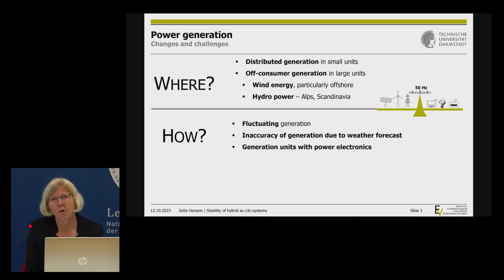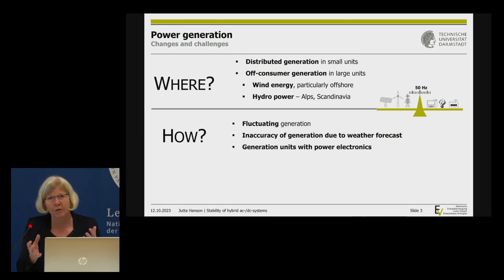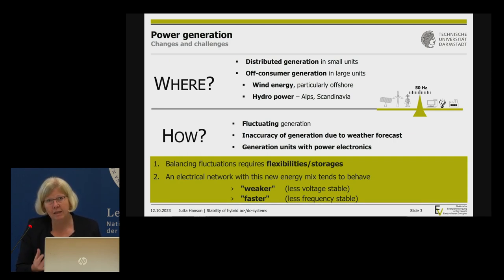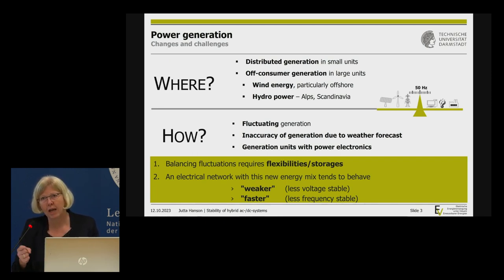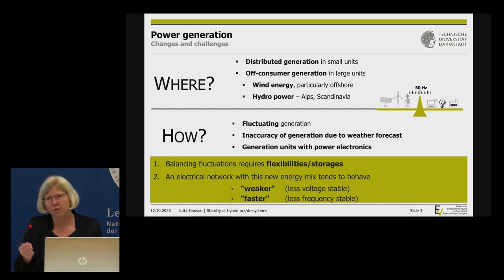One of the major aspects of my research: we have exchanged generation units. We no longer have synchronous machines with big shafts and a lot of inertia — we now have power electronics, which are very, very fast. We have to change the principles of our network. The network will be faster due to missing inertia, and it will be weaker — less stiff in terms of voltages.